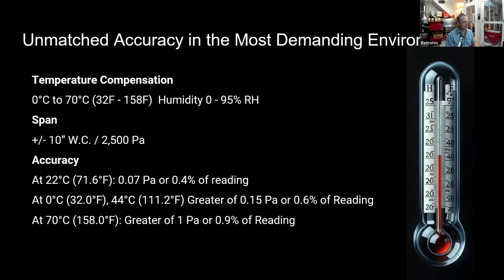That sensor and pressure switch can take some abuse as far as temperature goes. The span of it, just like the 32 and 32X, is plus or minus 10 inches of water. So for taking your static pressure readings, you've got plenty of room there to use it just like any other HVAC manometer.